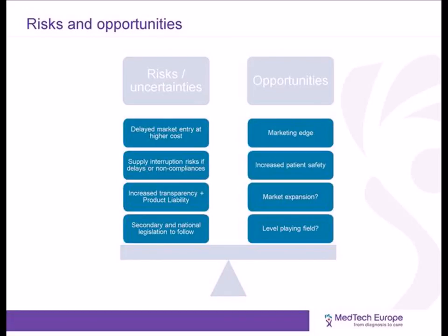Clinical data transparency is a topic which could raise both risks and opportunities. As in the pharmaceutical sector, the MDR will require that final reports of clinical investigations and summaries of those reports be publicly available via Eudamed, unless there is a given need to keep the information confidential and that need has been justified. If there is a repeat of the pharmaceutical sector's experience, redaction of commercially confidential information will likely need to be limited to information on the device's quality. This would, as a result, potentially put some significant sensitive information and proprietary data at risk of entering the public domain, for instance, regarding the design of a clinical investigation.